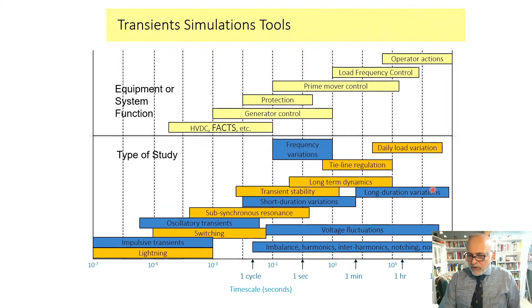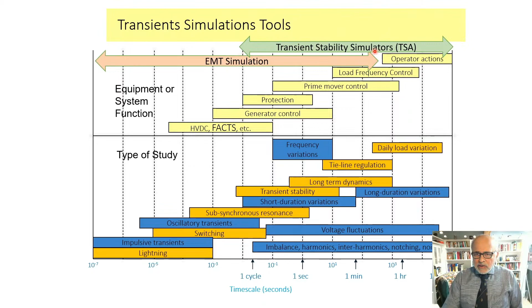The transient stability simulators used in the past generally model things into the 1 cycle range and above in terms of time. For HVDC effects and other things like that, we need electromagnetic transient simulation, which is the most detailed type of simulation. It can model basically the whole range of simulation studies we want to do, model switching more accurately, and also take care of slower frequencies. We'll concentrate more on EMT simulation and also hybrid simulation, combining transient stability and EMT together.